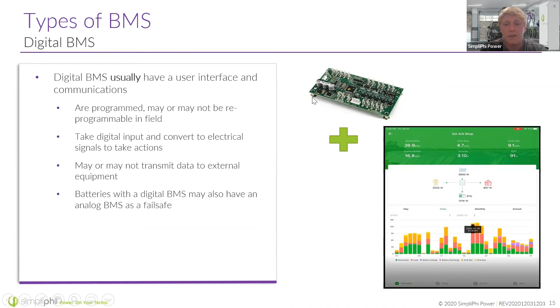A digital BMS takes digital inputs from a computer screen, a value like a 1 or a 2, and converts that to logic and signals to take actions. It might not transmit data, but sometimes it can. For example, our SimpliPhi BMS transmits data to the Sol-Ark, which shows it to the user on its LCD screen or on its PowerView monitoring software. So often batteries with a digital interface are going to have an analog BMS as a failsafe. Again, they can work in tandem.